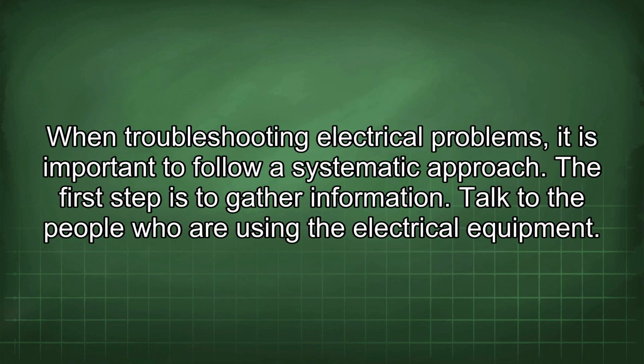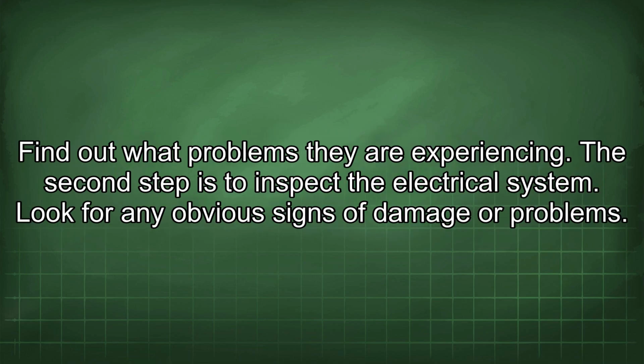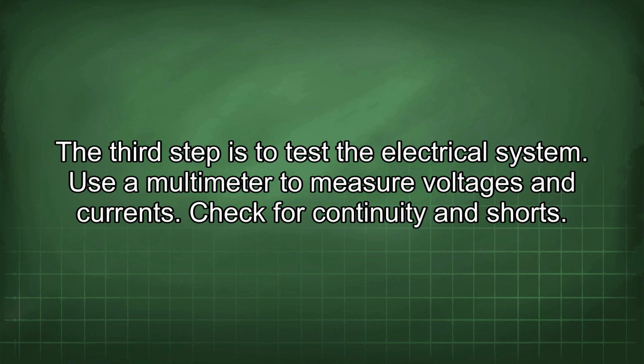When troubleshooting electrical problems, it is important to follow a systematic approach. The first step is to gather information. Talk to the people who are using the electrical equipment. Find out what problems they are experiencing. The second step is to inspect the electrical system. Look for any obvious signs of damage or problems. The third step is to test the electrical system. Use a multimeter to measure voltages and currents. Check for continuity and shorts.